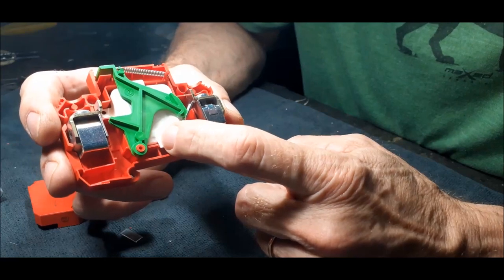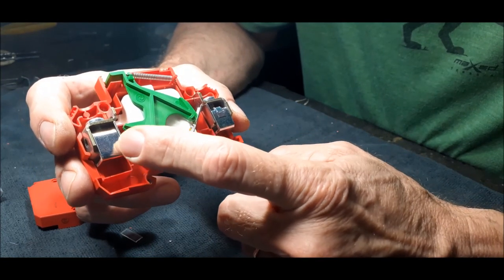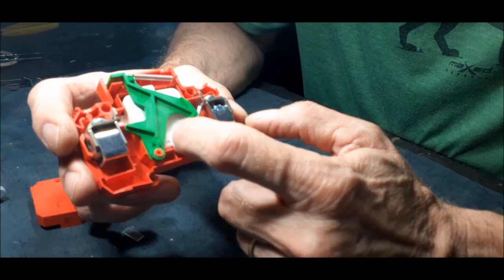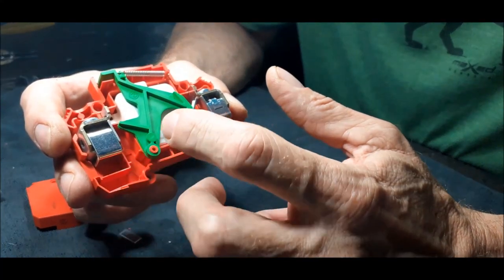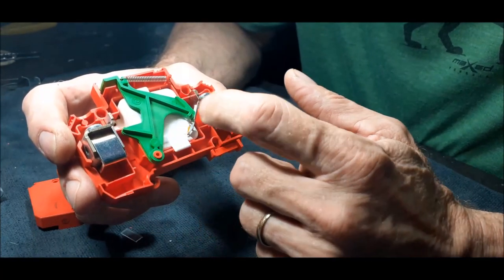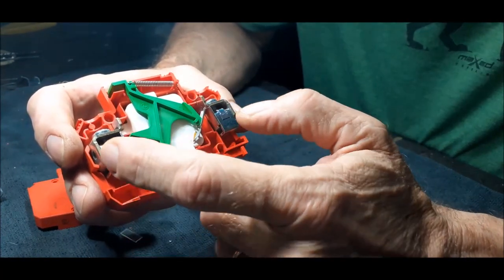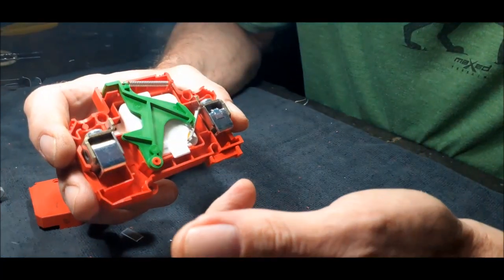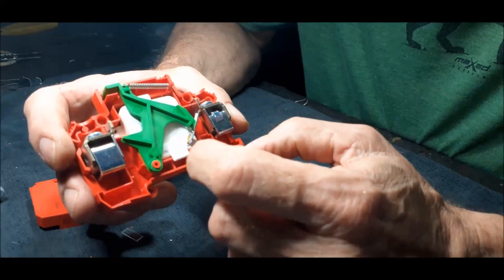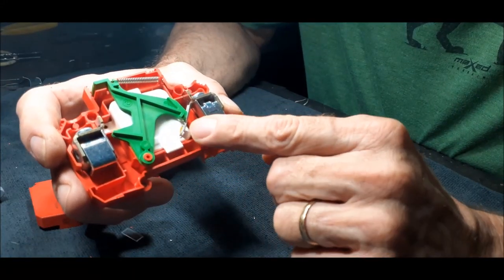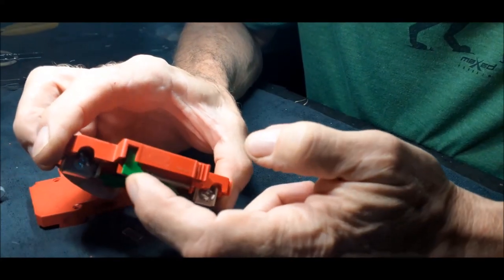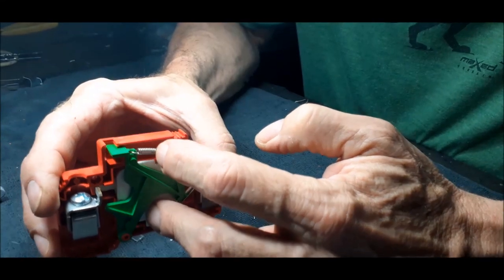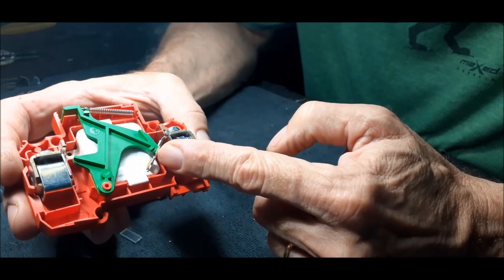There is a MOV, a metal oxide varistor. What happens when whatever it's spec for, like 275 volt, when this 275 volt spike should occur over the points, it should divert or short out the two points. I said it diverts it to ground. Then it starts acting. You'll see there's a little green plastic that gives you that green indication with a spring loaded. And this point is on that point there.